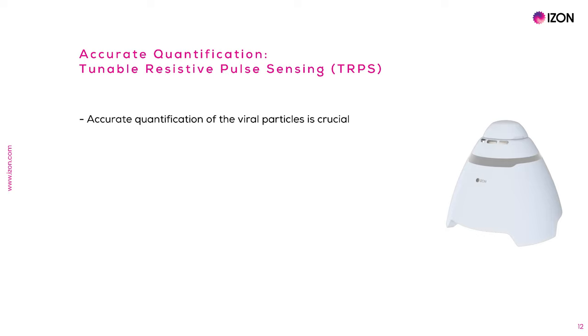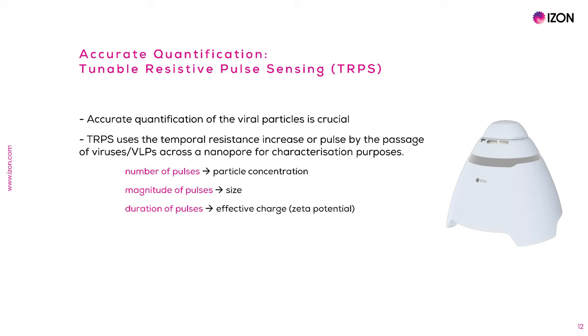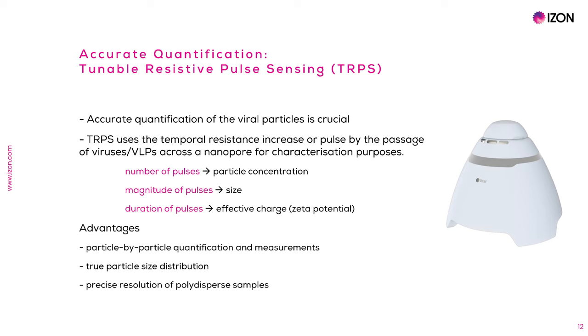The accurate quantification of viral particles is crucial across different aspects of virology. When viruses or VLPs are used as vaccines or therapeutics, quantification is required for quality control and reliable yield measurements. In contrast with optical methods, tunable resistive pulse sensing, or TRPS, uses the temporal resistance increase caused by the passage of particles across a nanopore. For TRPS size measurements, there is a linear relationship between particle volume and the magnitude of the resistive pulse generated; therefore particle diameters can be determined with high accuracy. Similarly, zeta potential can be measured for each individual particle by inspecting pulse duration, while concentration is derived from blockade frequency. TRPS provides single-particle measurements to deliver true particle size distributions and can precisely resolve polydispersed samples.